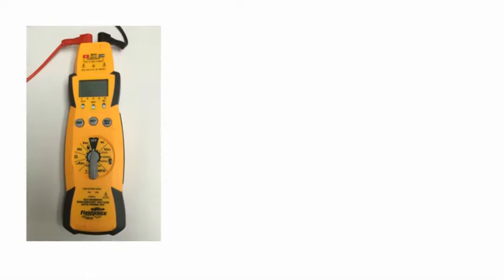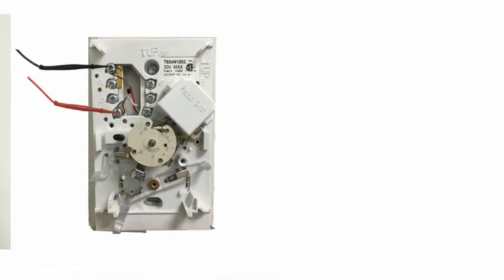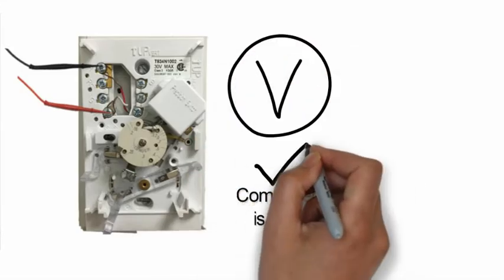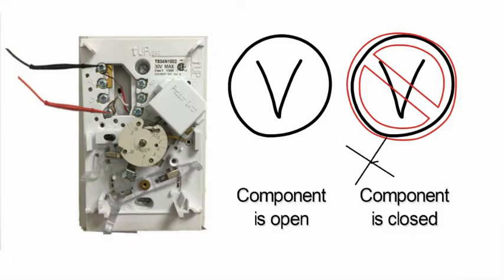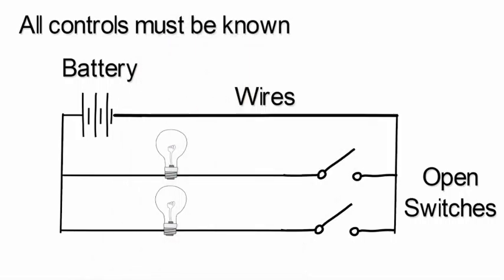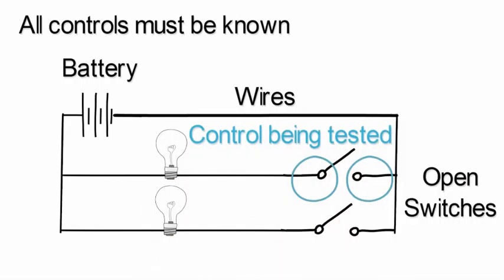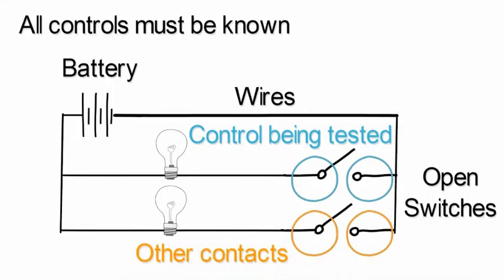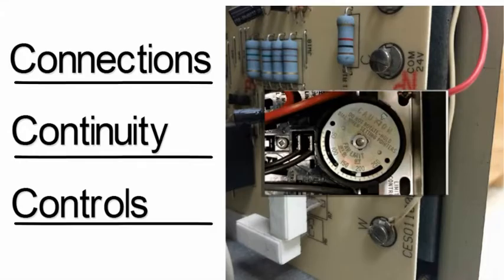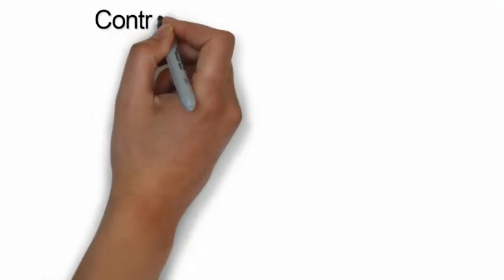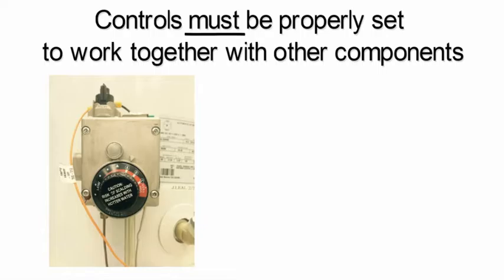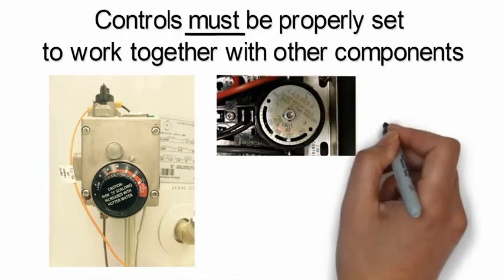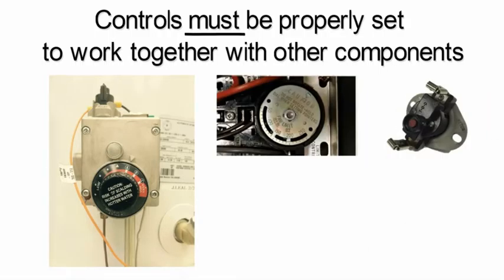If a multimeter is used to check continuity across a pair of contacts, the circuit must be operating. The meter should show voltage when the component is open and should not show applied voltage when the component is closed. All other connected controls must be known. If the contacts from the other controls are connected in parallel across the control being tested, the voltage test cannot be used unless the status of the other contacts is known. A controls check is the final area of circuit troubleshooting. A significant percentage of electrical problems can be traced to controls that are not properly set to work together with other circuit components. Correct settings can either be calibration settings that must be made or mechanical switches that must be set. Switches must all be set correctly for the control and its operating components to work properly.